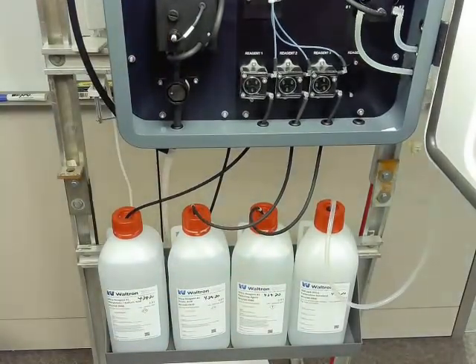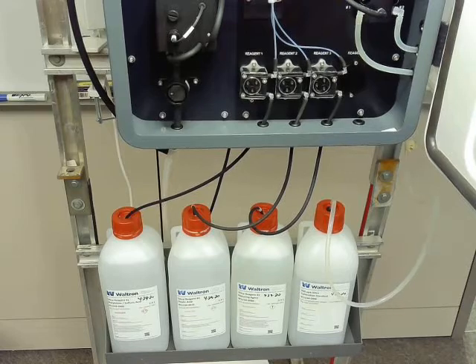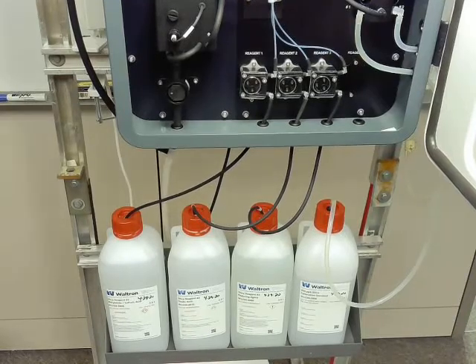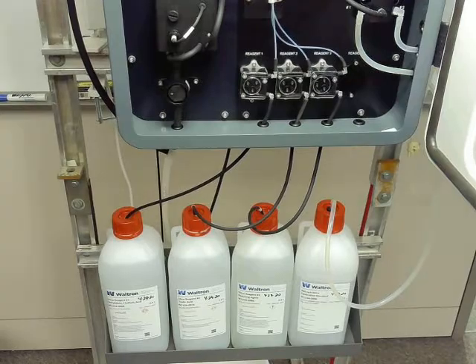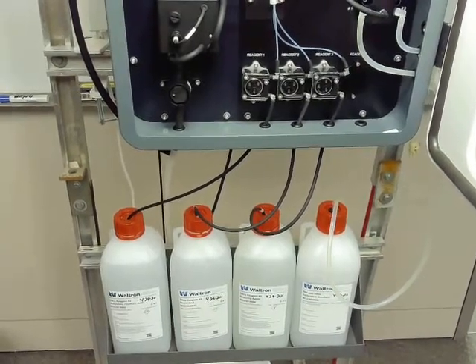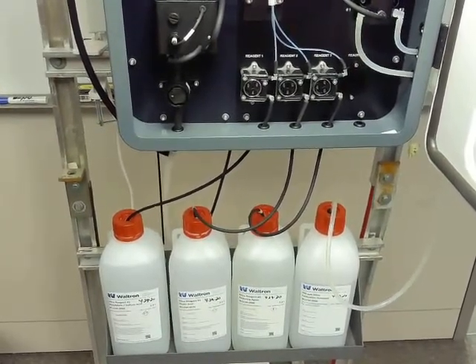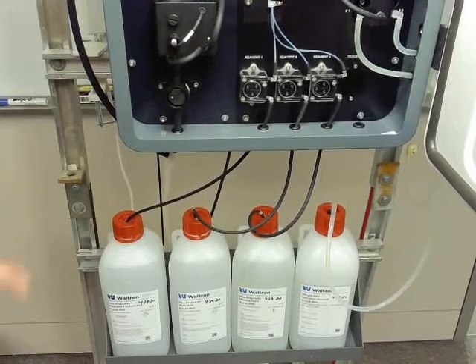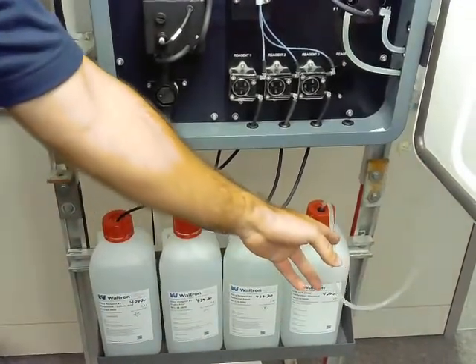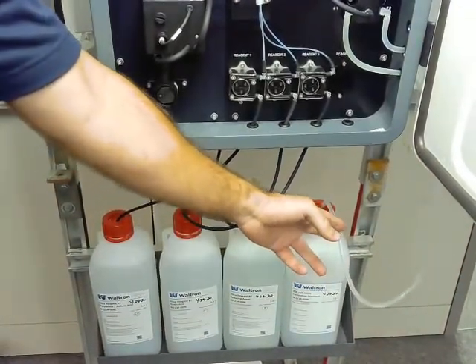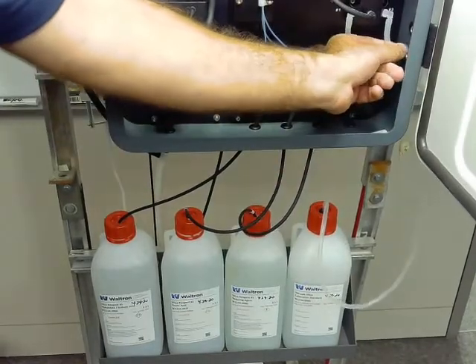Definitely worth noting that some of the reagents are slightly hazardous or corrosive. The SDSs with them will explain that, but it's not a bad idea to wear gloves and be mindful of where you're dumping or spilling them. Once we've got our reagent straws, again, I had already done the calibration standard earlier, but same thing with the calibration tube, which hooks into this second port on our selection block.